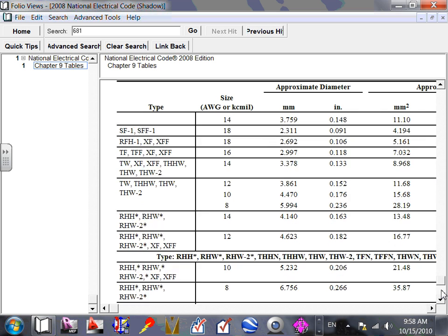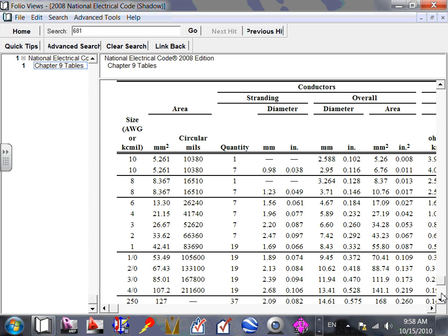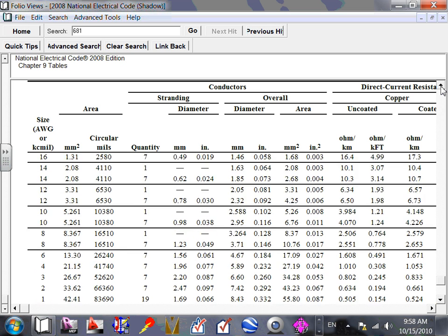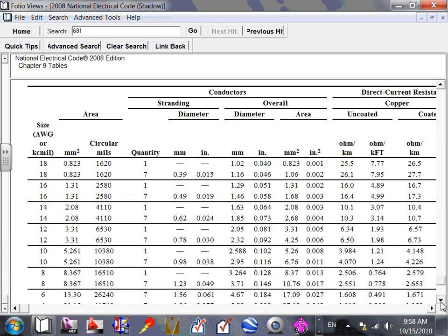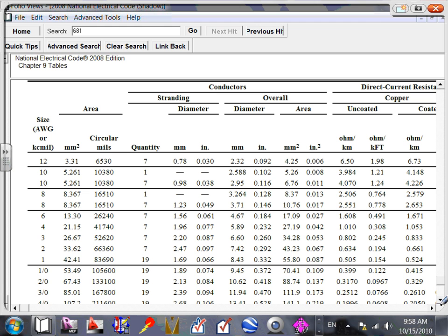Why didn't we just use the conductor size formula instead of going the roundabout way? You can, no problem. Except the code, table 8. The code is what you always have in front of you. So can you give me the impedance that we had?